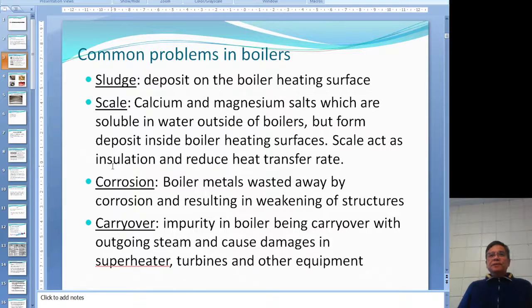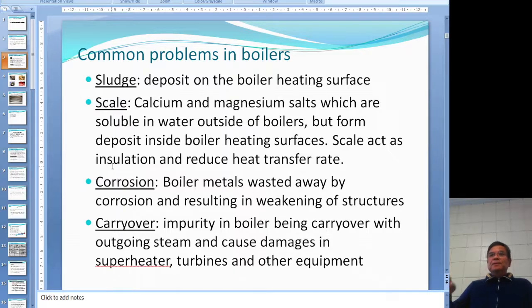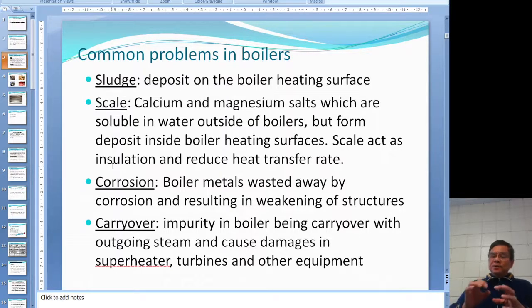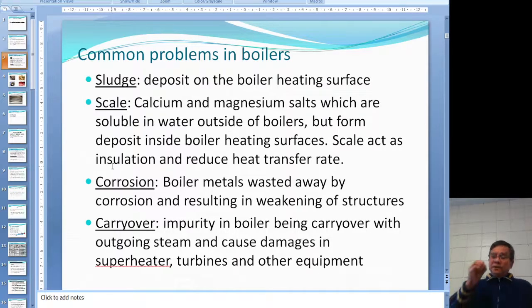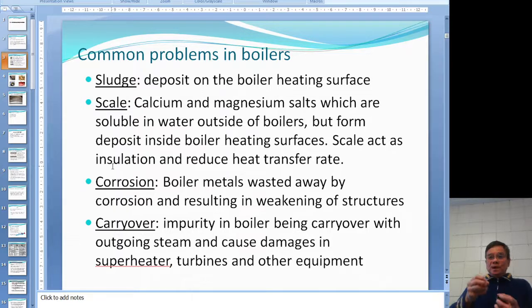Scale consists of different types of salts — mostly calcium and magnesium salts. They are soluble at room temperature but will deposit on the boiler heating surface. A layer of scale reduces heat transfer efficiency. Scale also causes localized hot spots, and the metal at those hot spots may fail — so it affects both economy and safety.